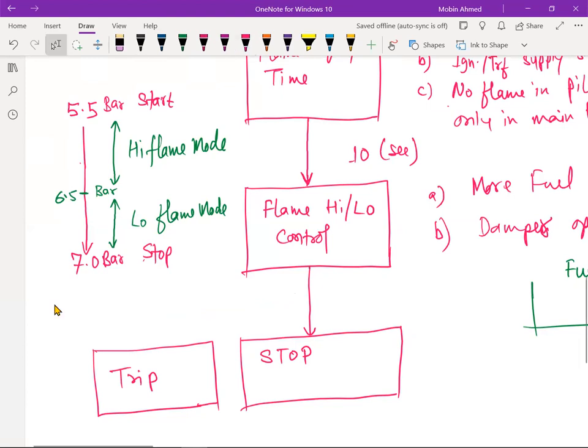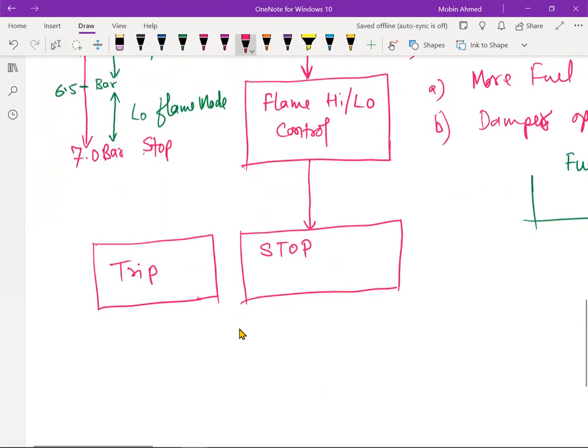Okay, so the flame is going to stop here. Stop means 7 bar, it is going to reach and the flame is going to stop. How is the flame going to stop? The same bypass valve, the FO bypass, will open, and the FO supply valve closes. Okay, so the flame is going to stop.